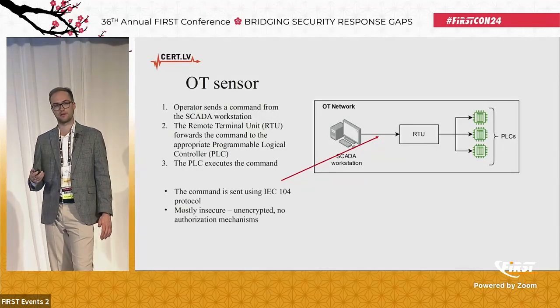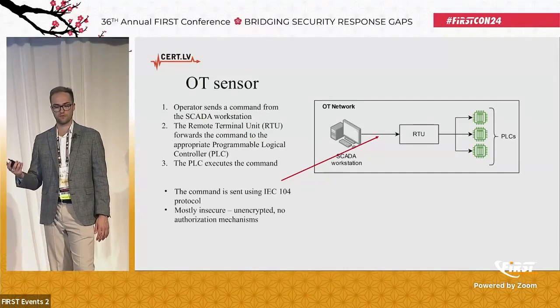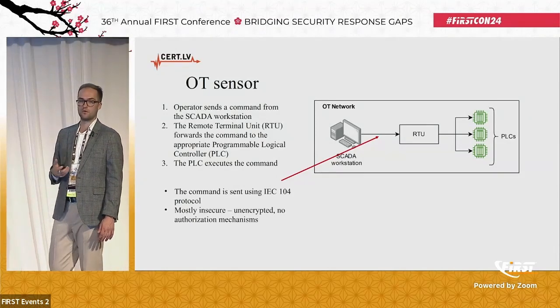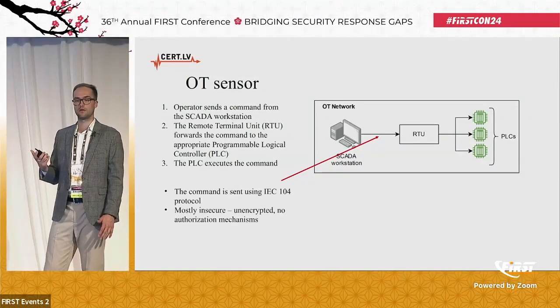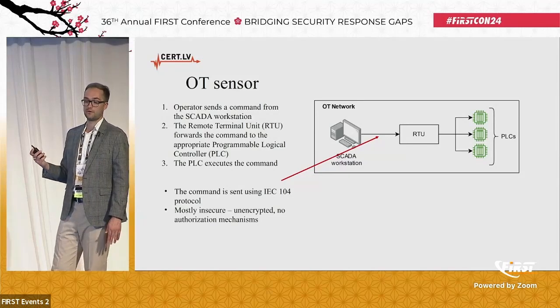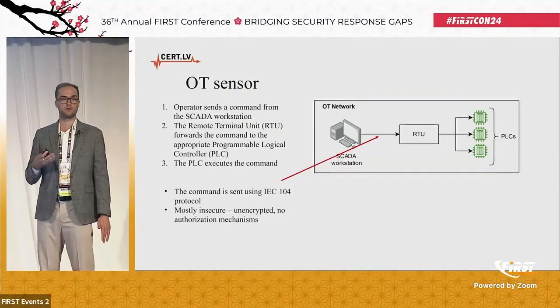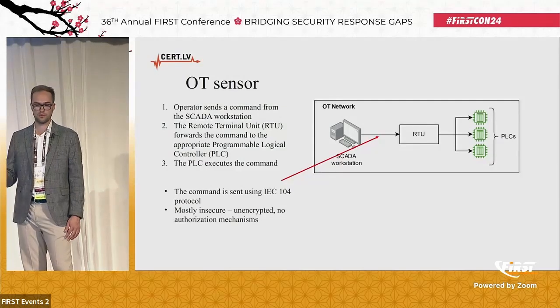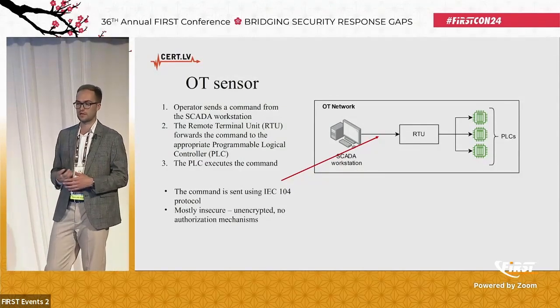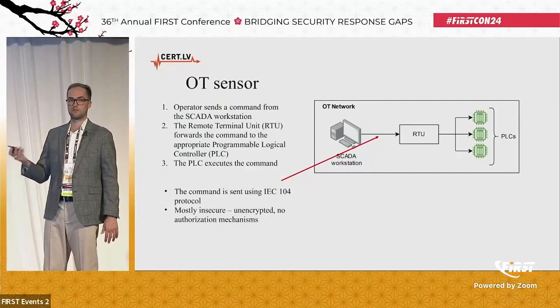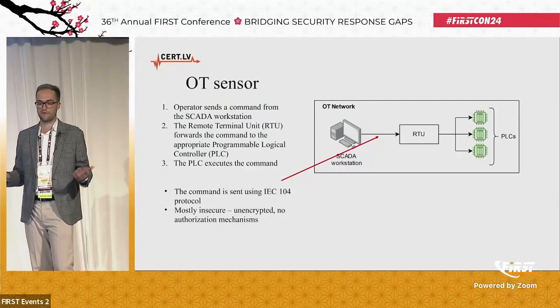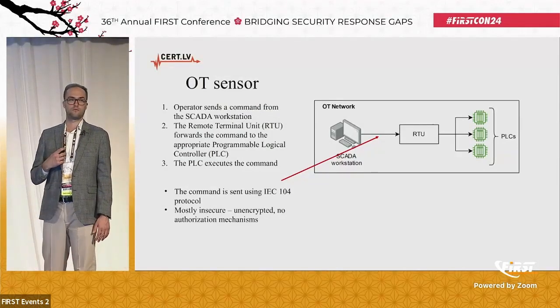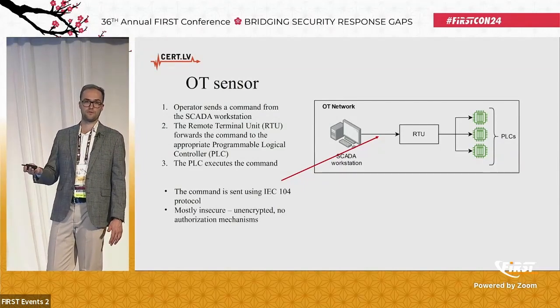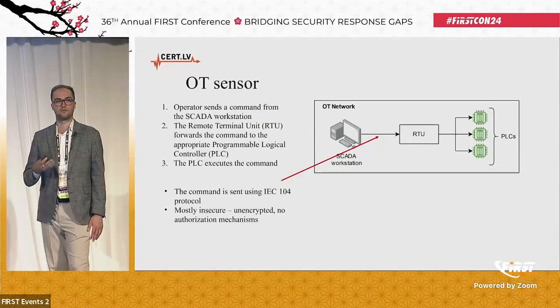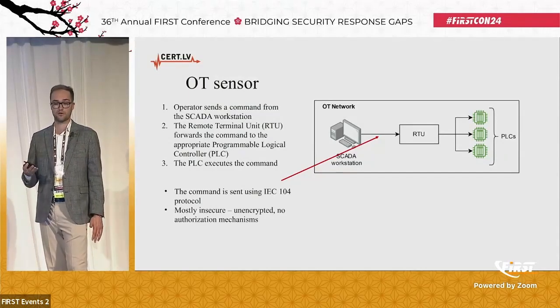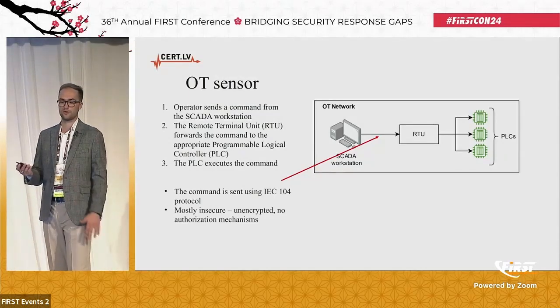Now this command is sent unencrypted using IEC 104. There are no authorization mechanisms on the protocol, and the security is most of the time implemented by the vendor. RTUs are sold by different vendors, so the security implementation depends on the vendor. Also, since it needs to be configured, it should be part of the engineer's job to configure it correctly so there are no security holes.